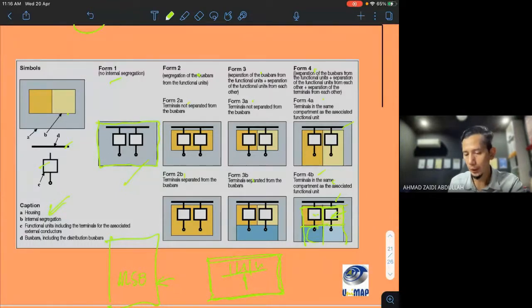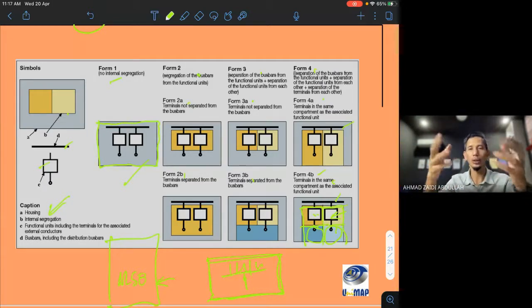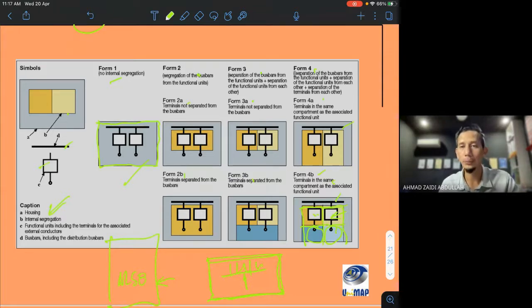So this one, form 4, below is the termination part, the connection cable to the protection part. Also, it provides a separate compartment. Because let's say during the termination there is some arcing, the arcing stays inside this compartment and does not affect the other components. So that's the good thing about Form 4B. It depends on you which type of form of separation you want to use for your project.